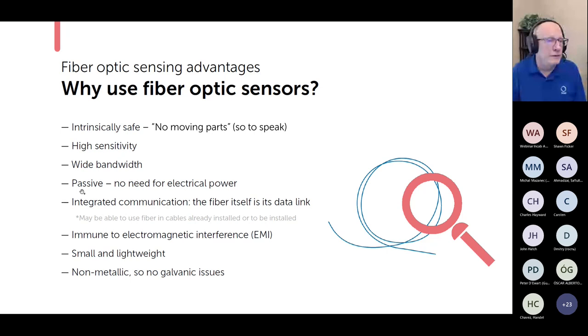They're passive when you're using distributed fiber optic sensors specifically. You don't have to power them. So if you're using a distributed system to sense temperature over 10 miles, you don't have to have electric power over that whole 10 miles. Now, you do have to have power at the beginning where you're generating the laser and where you've got the sensing equipment that actually detects the signal and processes it. But throughout that 10 miles of cable, you don't have to have any additional power.